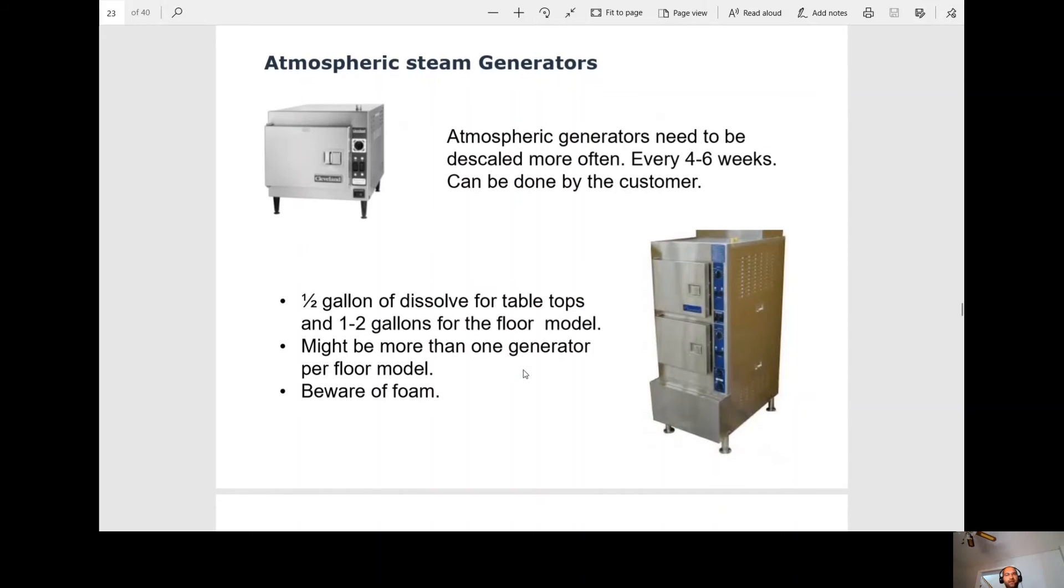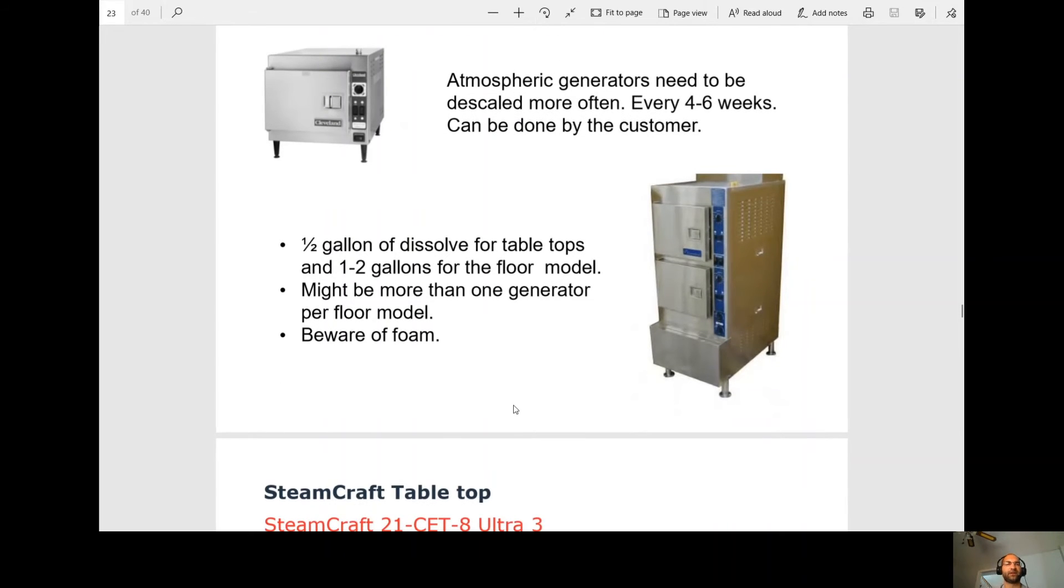Now we're going to go over to the atmospheric steam generators. So this is a self-contained unit. Atmospheric generators need to be descaled more often. They can be descaled every 4 to 6 weeks by the customer. So the customer will come up here, take this cap off, pour it in. Your customer can do that every 4 to 6 weeks. Half a gallon of dissolve for tabletops and 1 to 2 gallons for the floor model. So this would be the tabletop. This would be the floor model. As you can see, one's bigger than the other. That's why we need more dissolve in there.